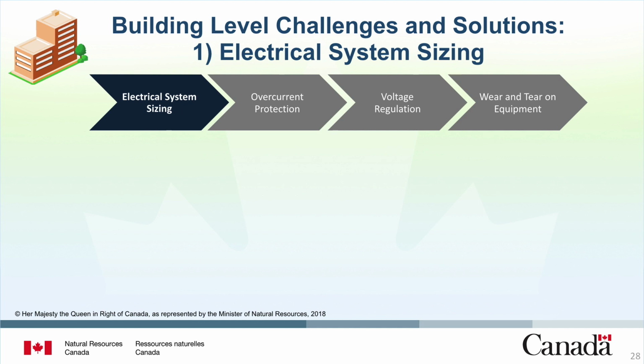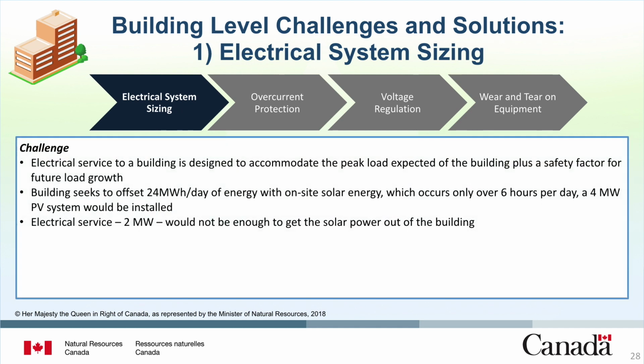Starting with the sizing of electrical systems to the building, the challenge is that the electrical service to a building is designed to accommodate the peak load expected of the building, plus a safety factor for future load growth. For example, a building with a 1 megawatt load might have a 2 megawatt service.